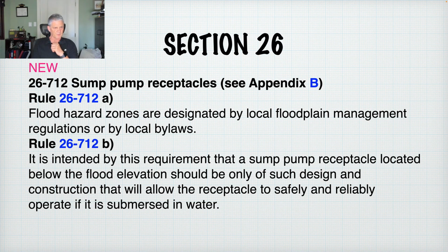Sump pump receptacle. 26712B, it is intended by this requirement that the sump pump receptacle located below the flood level elevation should only be designed and constructed in a way that will allow the receptacle to safely and reliably operate if submersed in water.